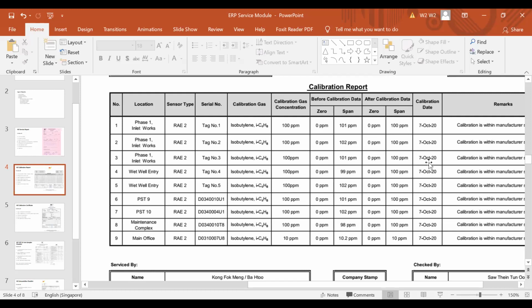For this one, when you use a calibration gas, your concentration is 100 ppm. So actually every equipment drifts. For the first one, you see that the span has drifted by 1 ppm. After we do the zeroing, some zeros do drift, for your information. So zero is sometimes 0.3, sometimes 0.2, but this time it is 0, 0. Okay, fine. So 100 ppm is with reference to the calibration gas. And you see that the last one, number 9, is 10, so the span is also 10.